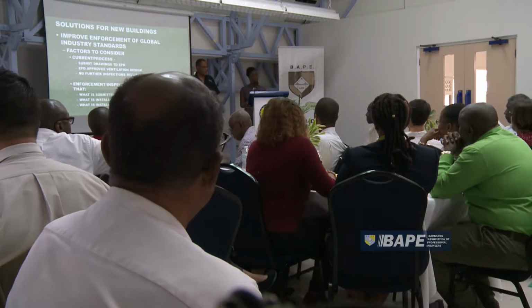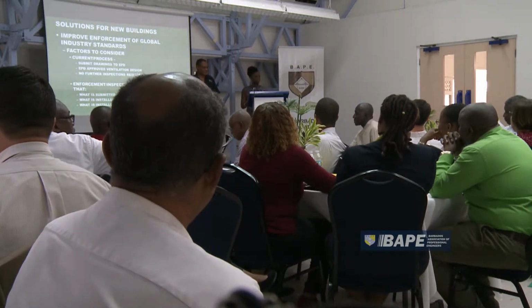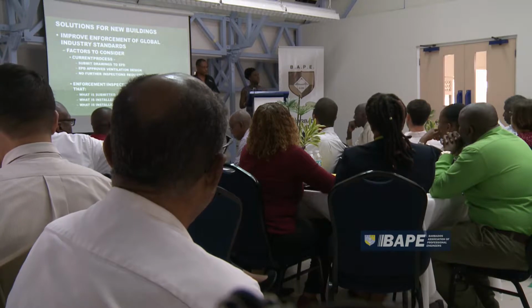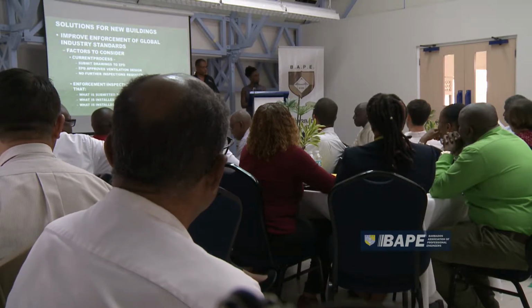If not, I have a question I can start off with, and it has to do with the commissioning of the equipment. When the equipment is commissioned, I am not certain that in all of the commissioning CFM readings are being taken. As part of my training, I believe you have to have some kind of tangible or empirical evidence to start with, because how will you know that the system is degrading over time if you don't have a value that you start with?